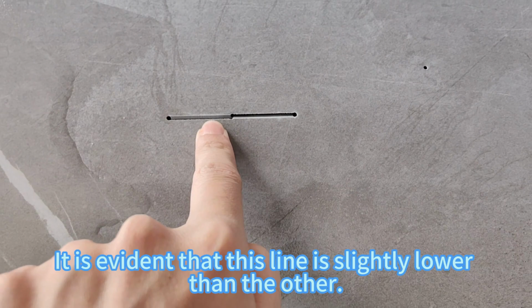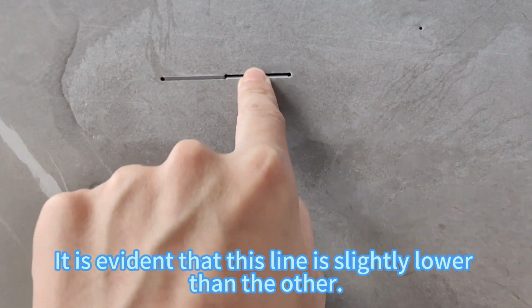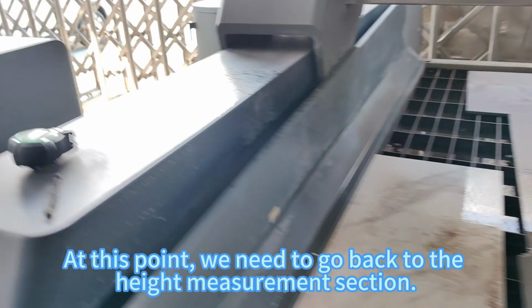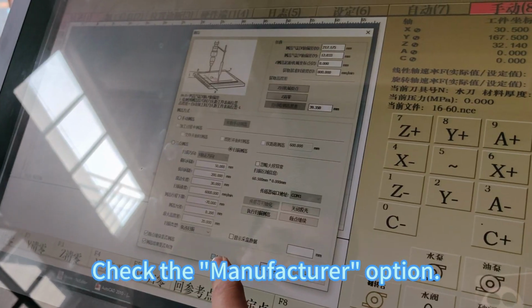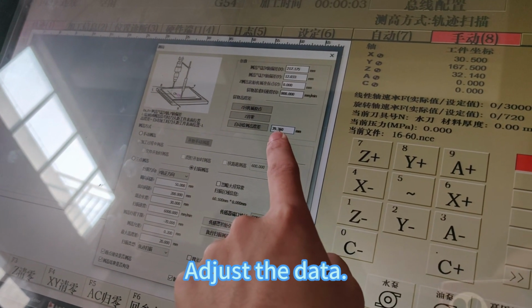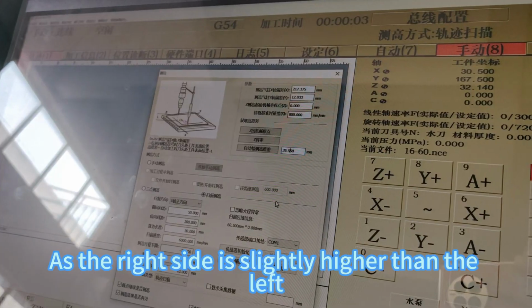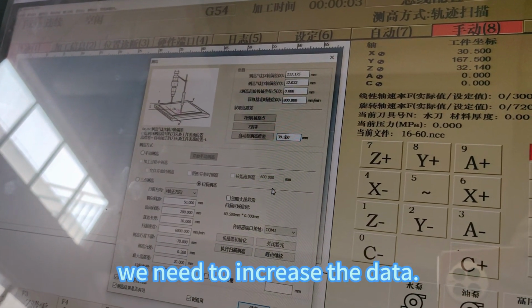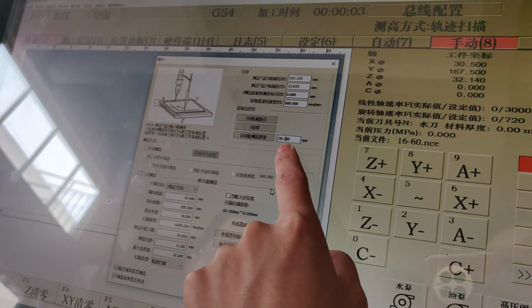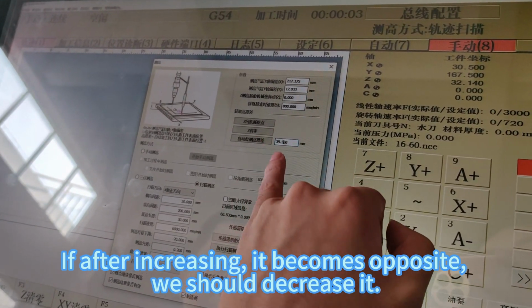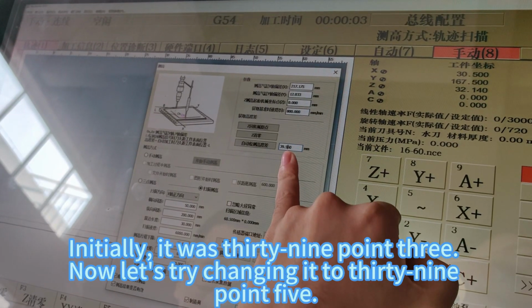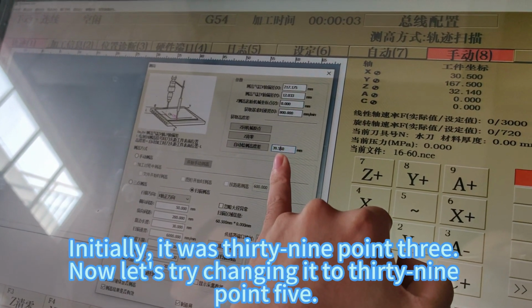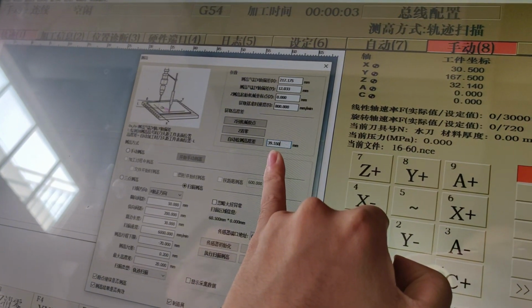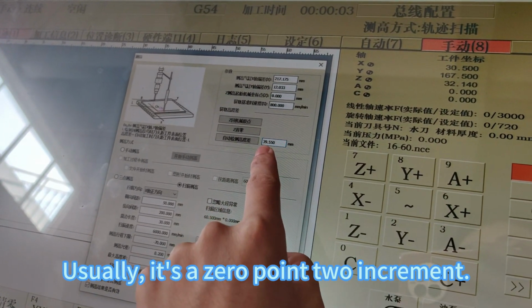Let's look at these two lines. It is evident that this line is slightly lower than the other. At this point, we need to go back to the height measurement section. Check the manufacturer option. Adjust the data. As the right side is slightly higher than the left, we need to increase the data. If after increasing, it becomes opposite, we should decrease it. Initially, it was 39.3. Now let's try changing it to 39.5. Usually, it's a 0.2 increment.